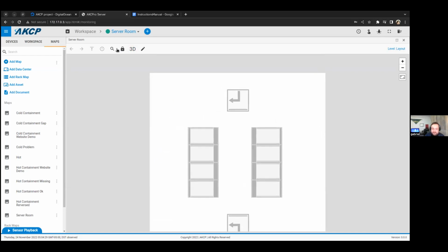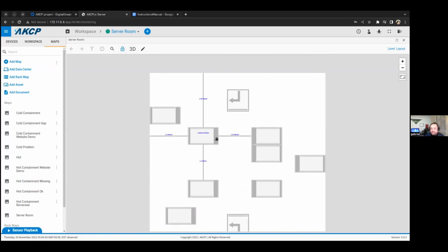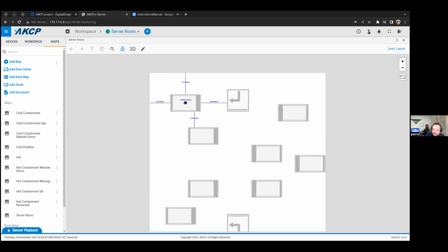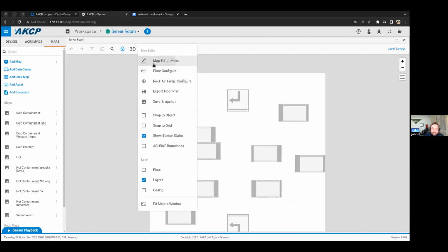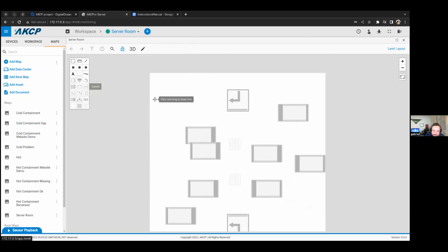Without containment, if I put the rack there, that rack there, the rack there, guessing the temperature inlet, the temperature outlet in the setup is really hard. So that's why we have the probe. When you have the probe, you don't have to guess, you just have to use the reality. But yeah, you can model everything you have in mind. So you can just do a really complex map with containment. You can use the front to back cooling unit. I think that was the question.